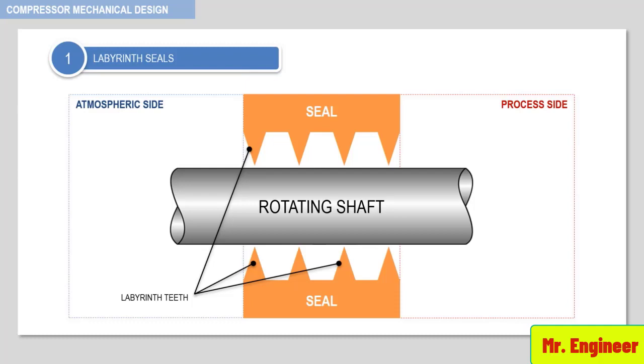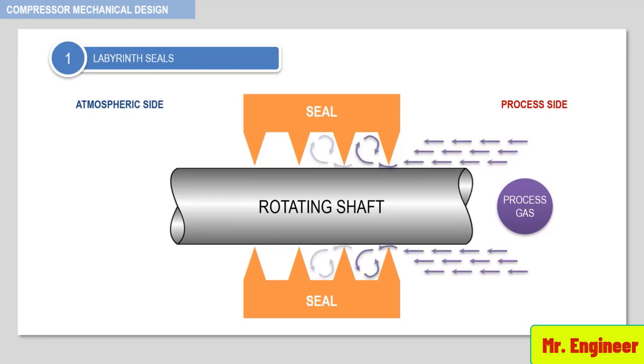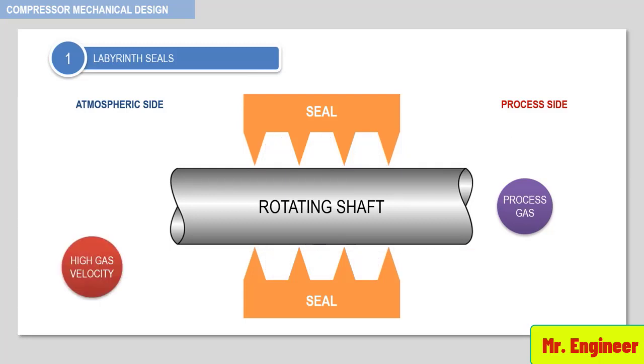As depicted in this example, when the process gas enters the space between the teeth, it slows down and changes direction. The resulting turbulence created restricts the flow of gas. However, if the gas velocity is very high, some of the gas does not change direction in a simple labyrinth seal and passes in a straight line between the teeth and the shaft, as depicted here.